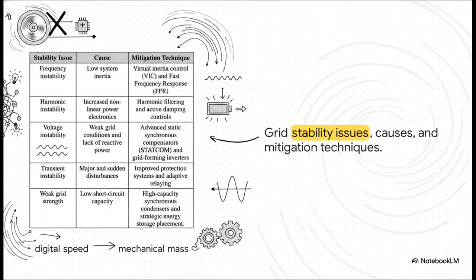To combat that frequency instability caused by low system inertia, they're deploying something called virtual inertia control. This is where smart inverters detect a frequency drop and instantaneously inject stored power to artificially emulate that physical resistance we used to get from heavy spinning metal. We're also seeing the rise of grid-forming inverters. These are devices that don't just follow the grid's frequency, they actually help establish and stabilize it. So we're replacing mechanical mass with digital speed.